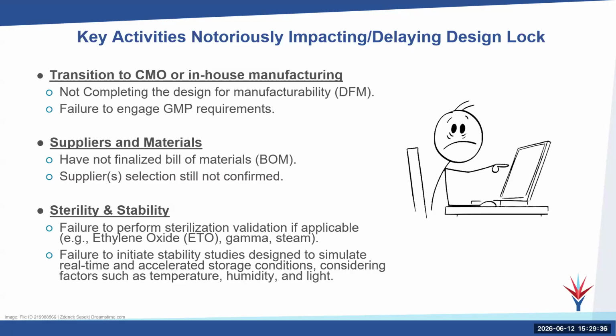Suppliers and materials, not having finalized your bill of materials or having selected who's going to be your ongoing supplier. Those haven't been confirmed. Or if you have no backup suppliers, that's also a weak link in your productization that can really slam you into a wall. If your supplier gets into trouble, or they go out of business and you don't have a defined backup supplier for a key element of your product, you can actually put yourself into a really serious situation. Sterility and stability, those are also things that we sometimes forget about. Failure to perform sterilization validation, failure to initiate stability studies designed to simulate real time. Those get started late or not at all, and you've got a gap. And again, another serious delay in your product.